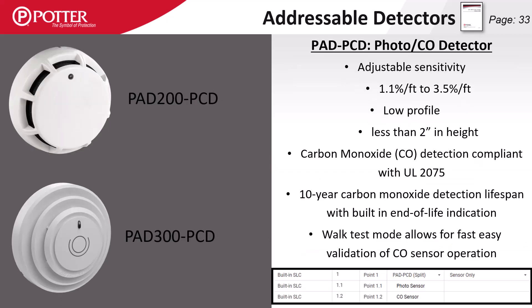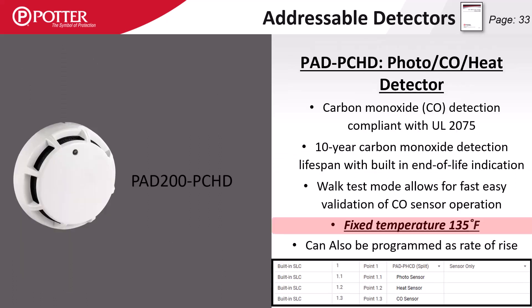The PCD is the combination photo and CO detector. Both series of detectors have a 10 year lifespan. The PCHD is all three detector types in a single detector head — a photoelectric smoke, a CO, and a heat detector — providing three separate mappable points.